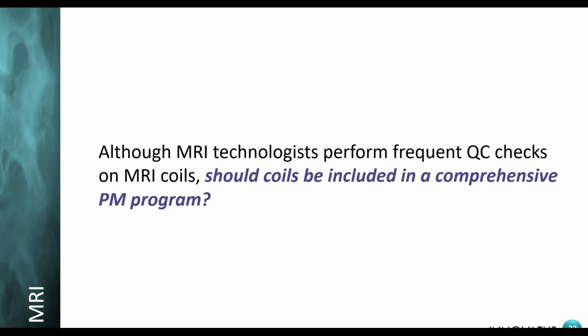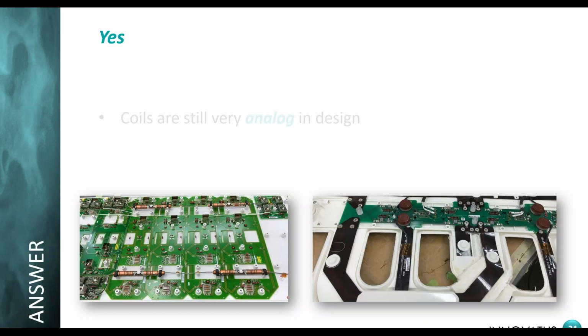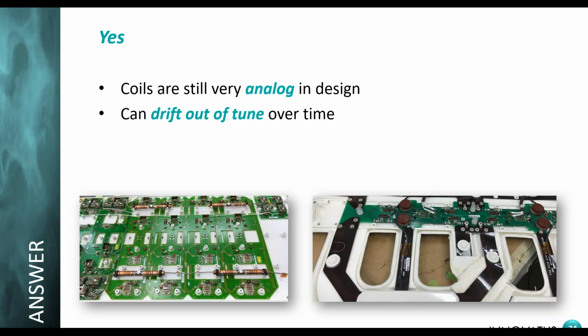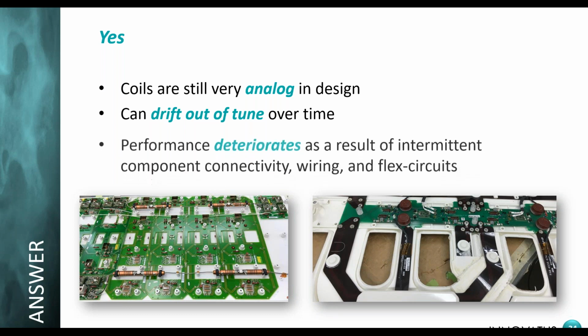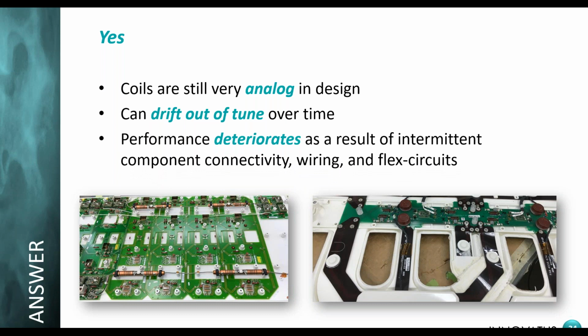So although MRI technologists perform frequent quality control checks on MRI coils, should coils be included in a comprehensive PM program? Do we want to do PMs on coils? You got a 50-50 shot. No PMs on coils? We actually want to. They're very analog. They can drift. You had a 50-50 shot. They can drift out over time, and the performance will deteriorate.